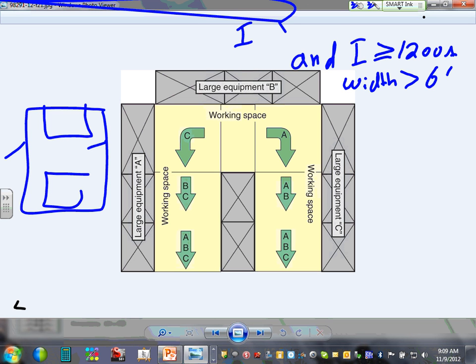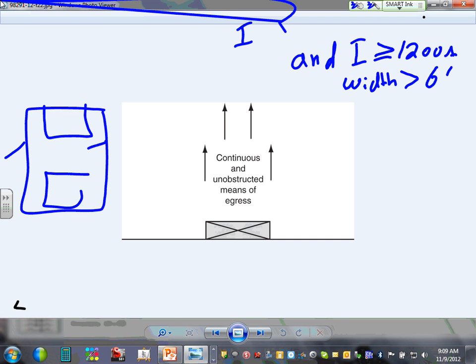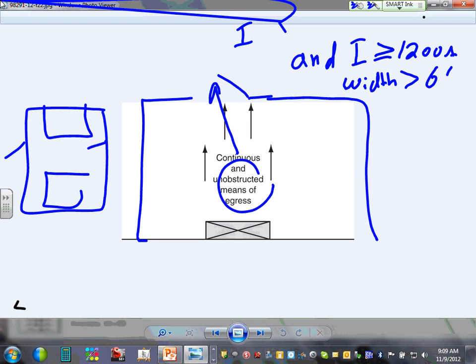So in this case, here's my switch gear. You don't want to trap people around, so you have to have different entrances for your switch gear. Let's look at the other one. Continuous and unobstructed. The exception, guys, if the door looks like this, and your switch gear, if the door looks like this, and you orient your switch gear this way, then it just flows all the way around, right? It's unobstructed. If there's a ball of fire chasing you, you have only one way to go. If you put it right here, then you have to have 2 doors, 1 here and 1 here. Can you guys see where you're orienting the equipment require you to have different doors?